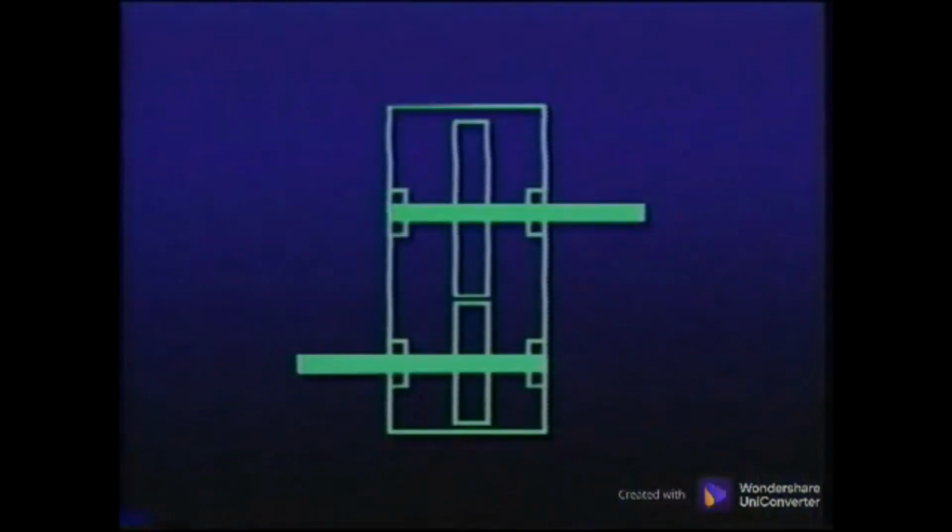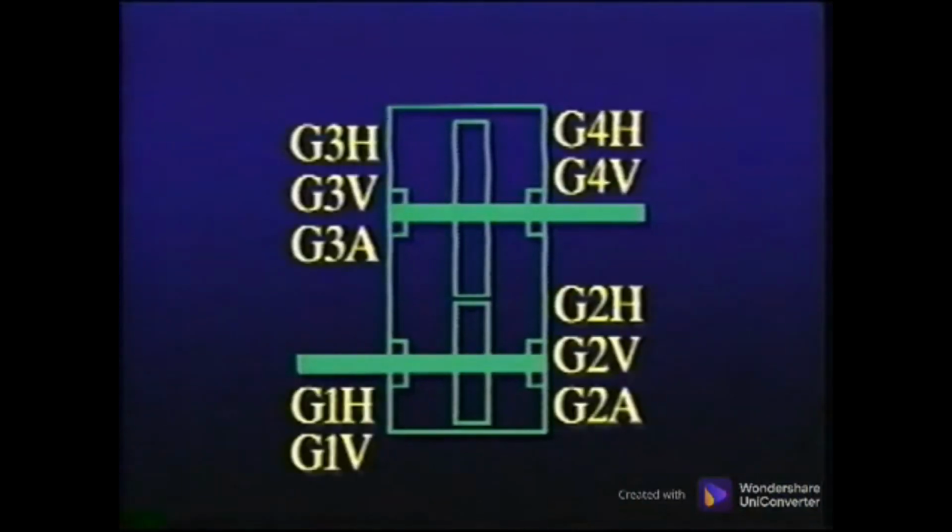Another helpful tool is a simple diagram of the gearbox showing each shaft, the measurement point locations, and the gear locations. It is very important to know the exact input shaft speed and the number of teeth on each gear. These will help in determining exact gear mesh frequencies and other indicators.